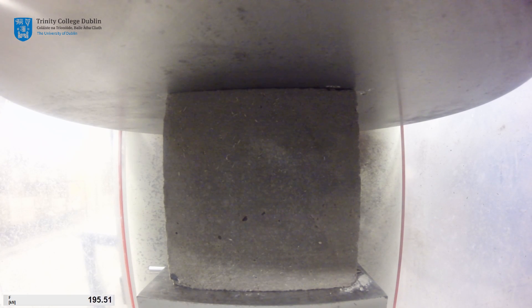Throughout the test, the current force being applied to the specimen is displayed in the bottom left-hand corner of the monitor. A plot of force versus test time is also displayed and updated in real time. The test machine continues to apply force to the specimen at the set loading rate until the specimen fails.